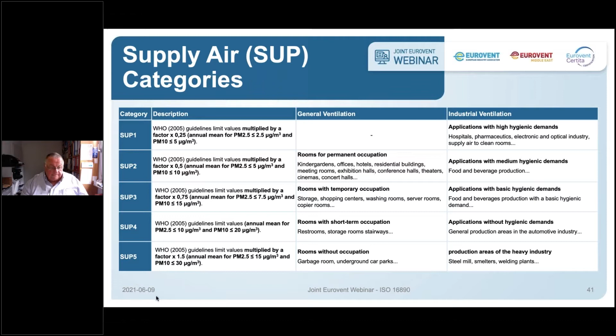How to choose a filter now? We have here the outdoor air quality. I've explained that. And we are assuming for our example an outdoor air quality of 3. So we are anywhere in that line. And we want to have a supply air quality 2, so we are in that column. This shows we have to use an ePM1 level filtration. ePM1 level filtration of 80%, because we have outdoor air quality 3 and we want a supply air quality 2. We end up at an ePM1 value of 80%. That's what the filter should bring.